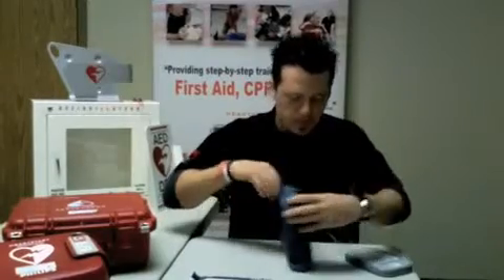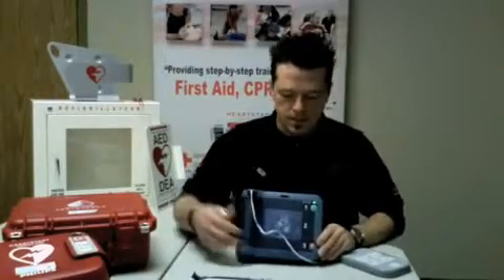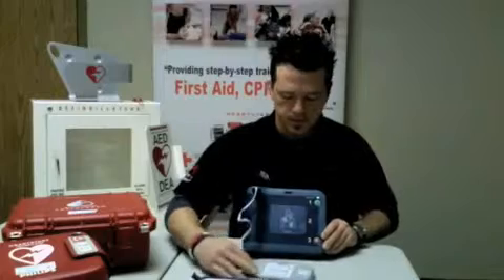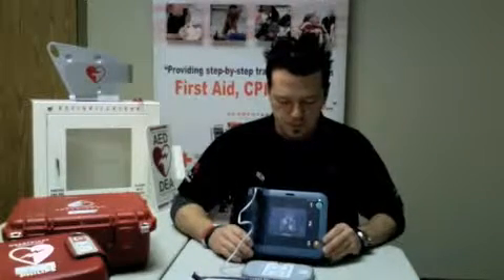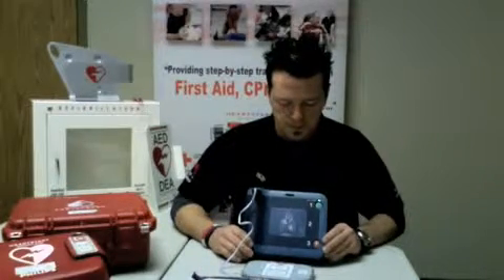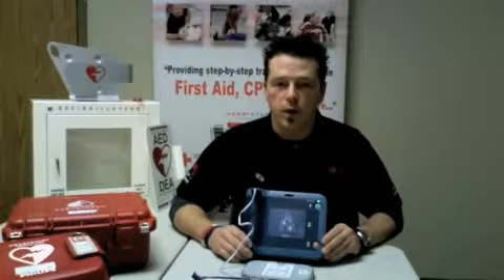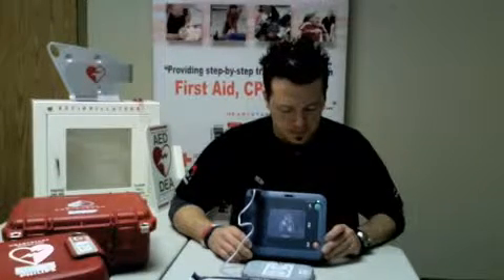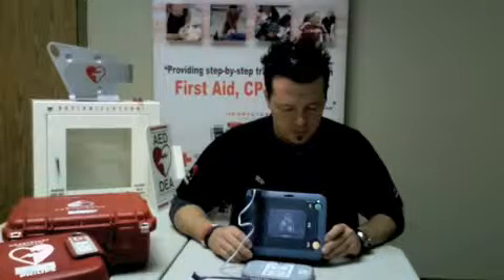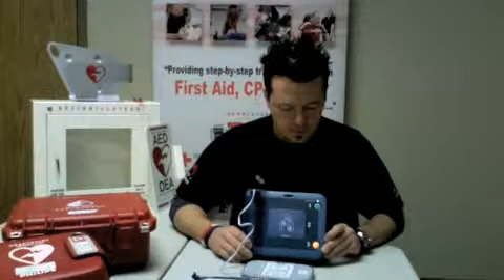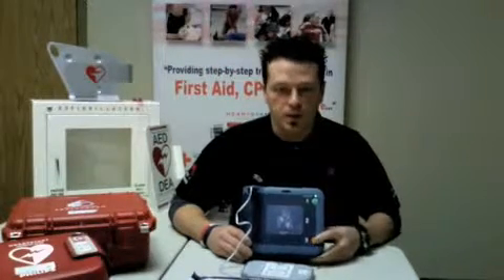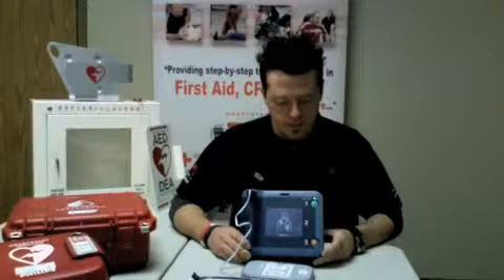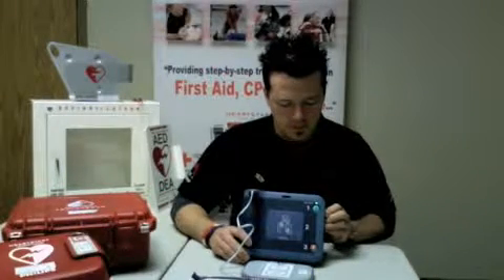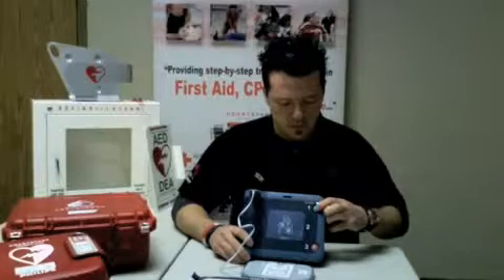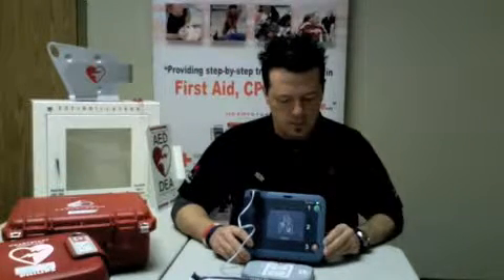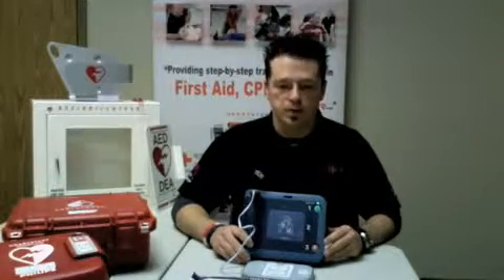Beginning self-test. If this is an emergency, press the green on-off button. This is not an emergency, so we won't press the green button. Shock button test. If the orange button is flashing, press it. We'll press the orange button. Verified on-off button test. Press the green on-off button now. Verified.